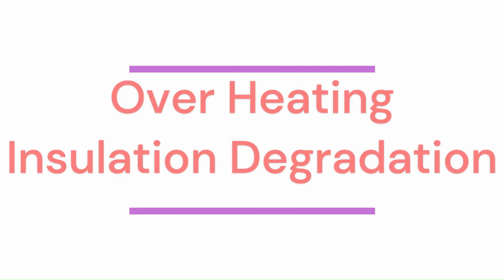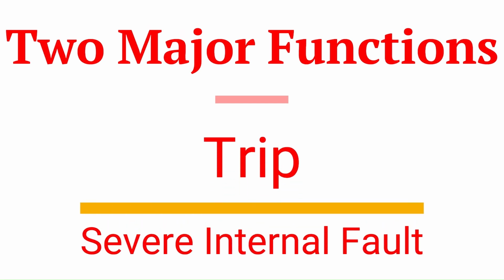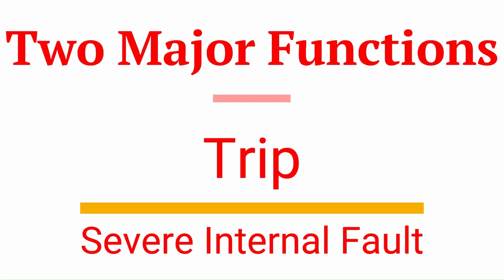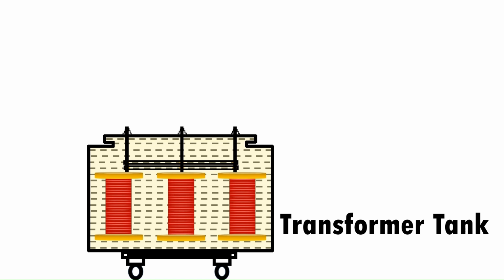The second function of the Buchholz relay is to give a signal to the trip circuit when there is a severe internal fault, like a short circuit. Hence, it is used to disconnect the circuit from the supply. Buchholz relay is installed on the pipe which is used to connect the transformer main tank and the conservator tank.